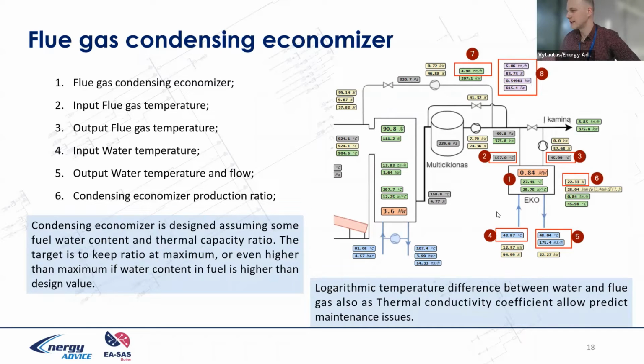Another is the status of the economizer, because the yield of the economizer depends not only on the water content in the flue gas, in the fuel, but also on the supply water and temperature, and also on the heat exchanging efficiency. Sometimes you see lower or higher yield of the condensing economizer, but you never know why. What is the reason? Okay, it's better to know when it's bad. So the efficiency numbers allow us to understand: is it time for cleaning, or is it just water content in the fuel and the efficiency is okay?